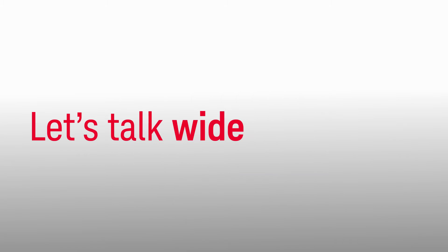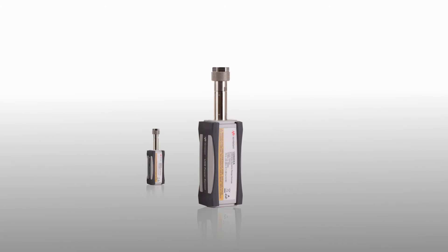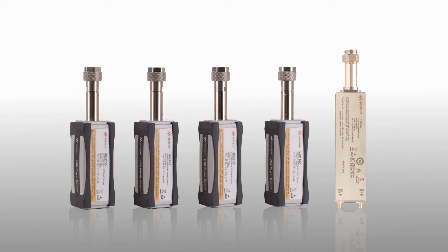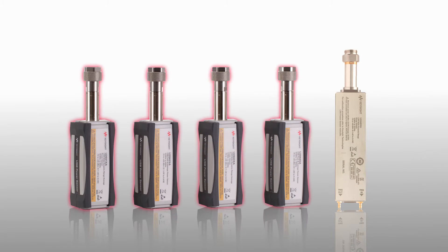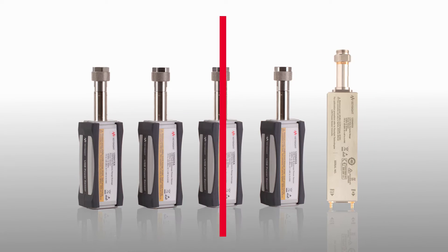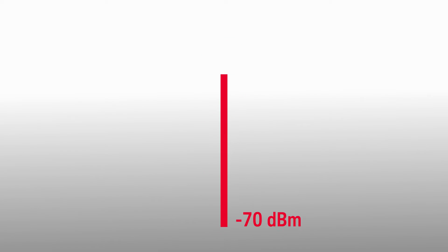Let's talk wide. The U2040 X-Series includes five models: four USB based models and one LAN based model. This family of sensors has the widest dynamic range of any power sensor on the market, from minus 70 to plus 26 dBm.